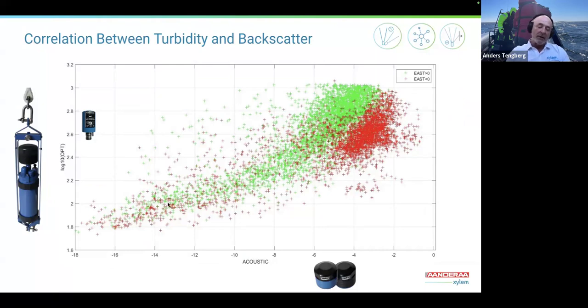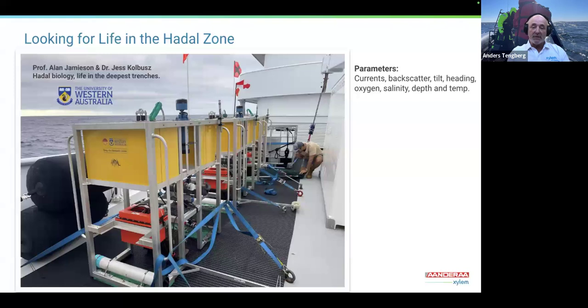This relation can then be used, because the acoustic Doppler current sensor can basically work even with a lot of fouling on it. We have seen sensors that are 3 times bigger in size after being fouled, and they still work perfectly well. So once you establish a relation between turbidity and acoustic backscatter, you can continue to use the acoustic backscatter as a proxy for turbidity, even when the optical sensor starts having fouling issues. That's one big advantage of that sensor.